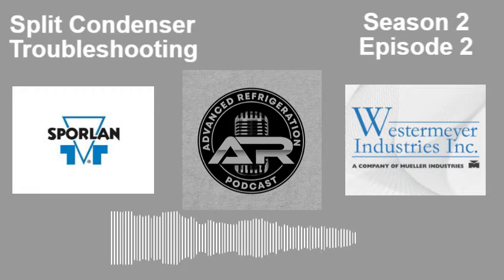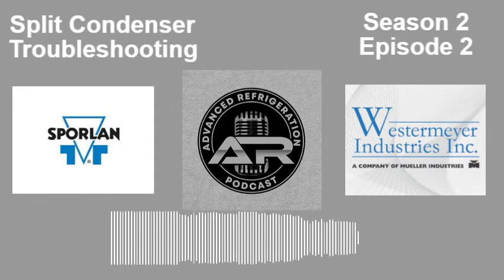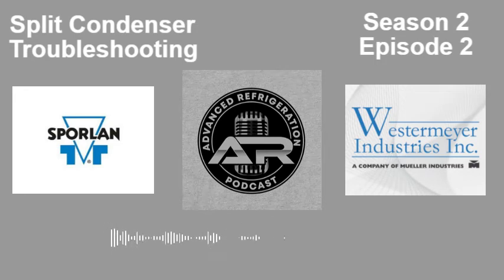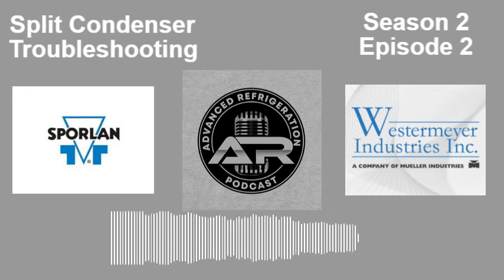Actually, it's funny that you mentioned that, since we're talking about this now. A guy was at a store, and he sent me a picture of the receiver levels. Both of them were at 50% at one point, and then it just dropped off to nothing. He was intermittently calling me back every time he'd find something new, and I said, you were at 50%. There's no way that just disappeared unless both racks got hit by a forklift at exactly the same time. You'd have to check the split side of the condenser, and lo and behold, I didn't get a phone call back after that. So I think he found the problem.